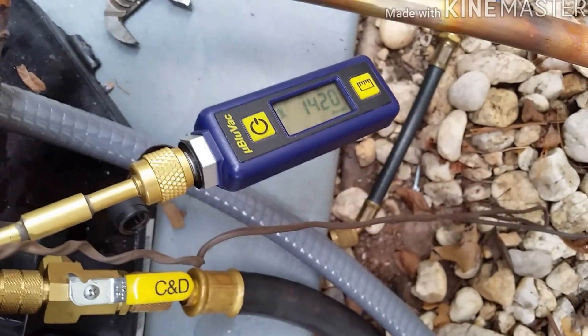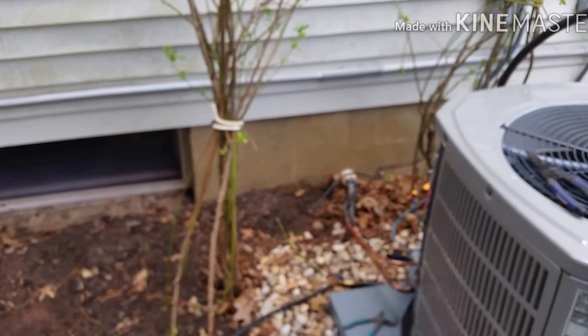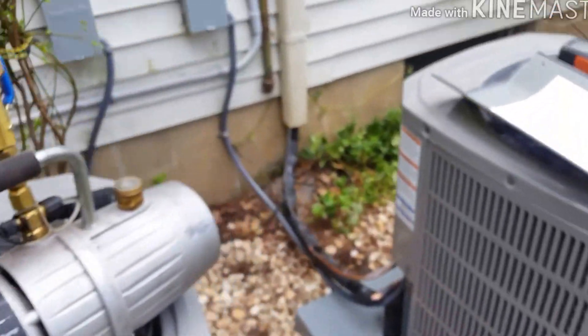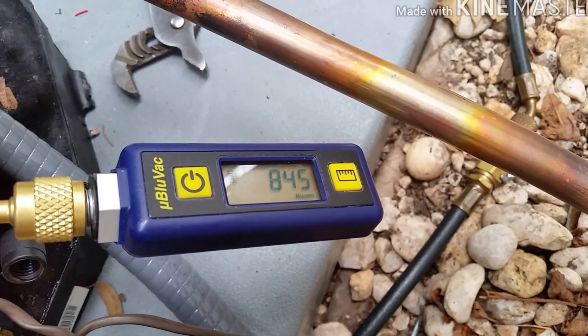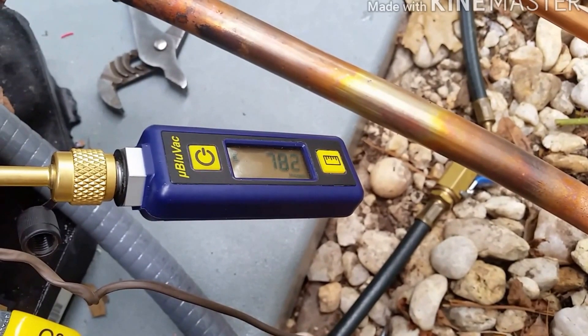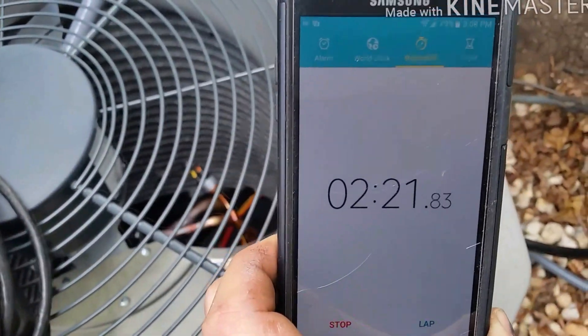We are moving pretty fast. This line set is not long — it goes through the basement wall here and the furnace is maybe five feet in front of the wall. Not bad for one hose. You guys looking for a cheap, quality vacuum micron gauge? This little bad boy is nice — small and good quality. Almost 230 microns already.